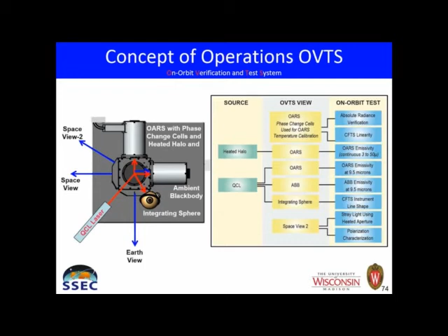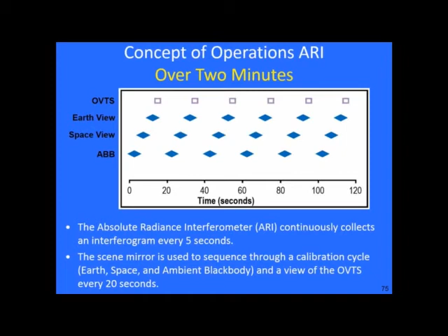So it continuously collects interferograms every 5 seconds, and the scene mirror is used to sequence through Earth, space, ambient, black body, and then a view to this on-orbit verification and test system. That view to this on-orbit verification and test system can be mixed and matched. You could have different radiance levels, but the idea is that it always fits into the cycle, but it could be a different thing that you're looking at.